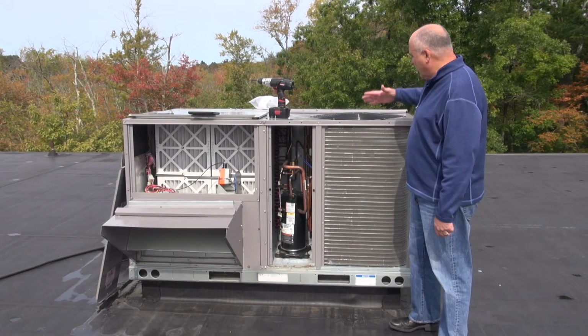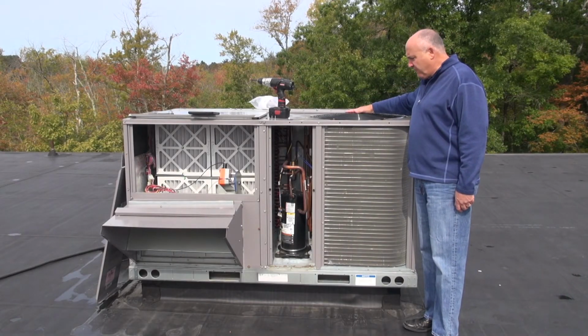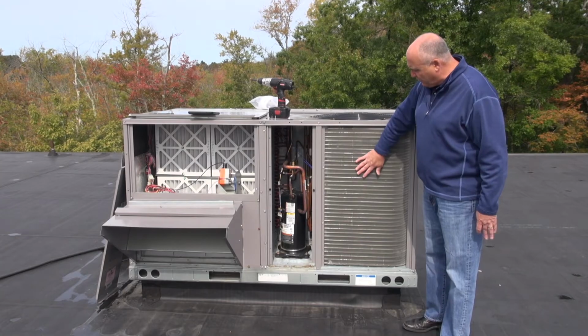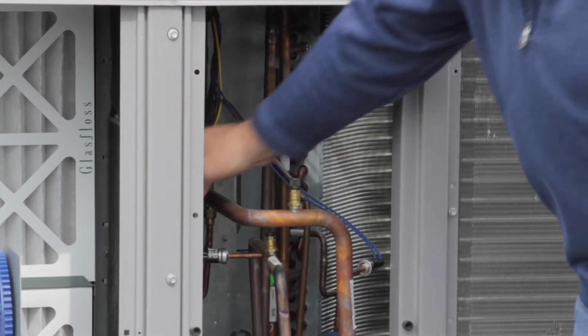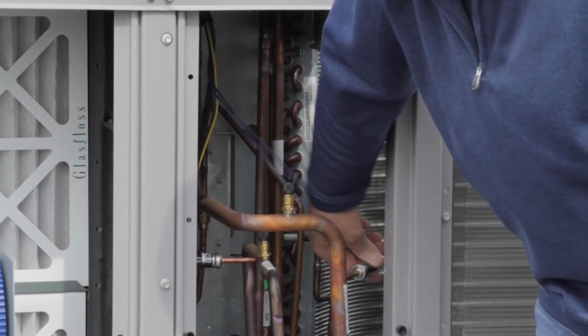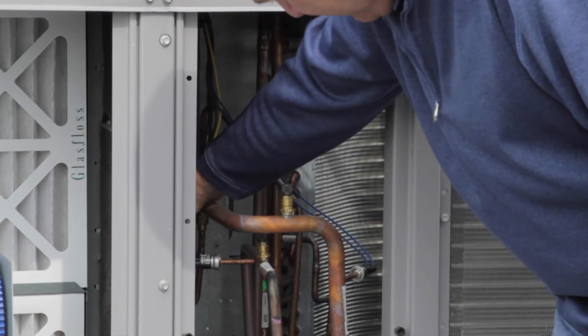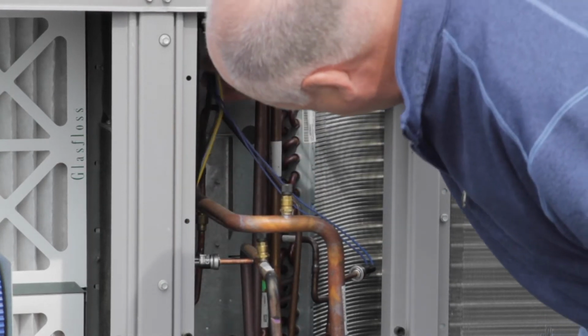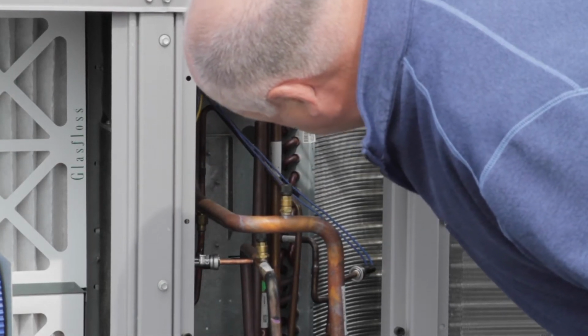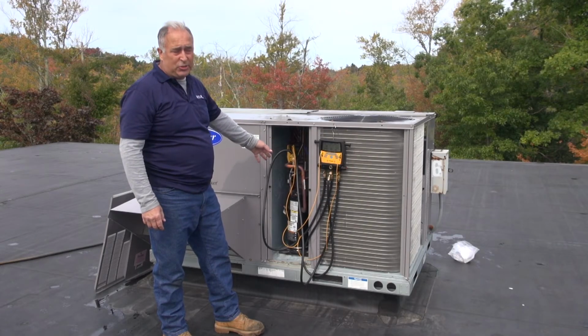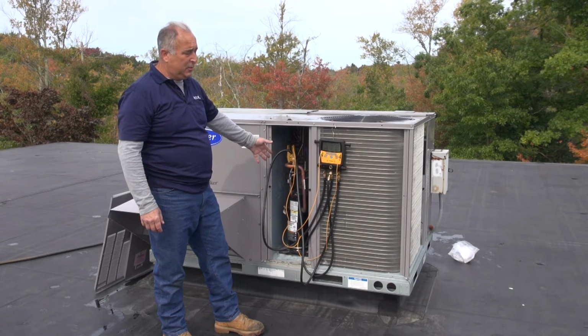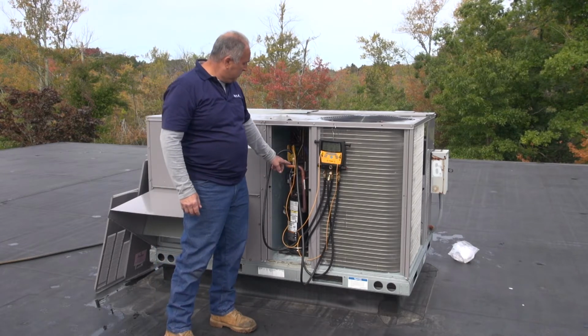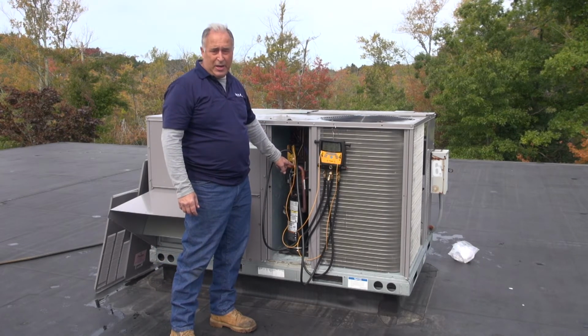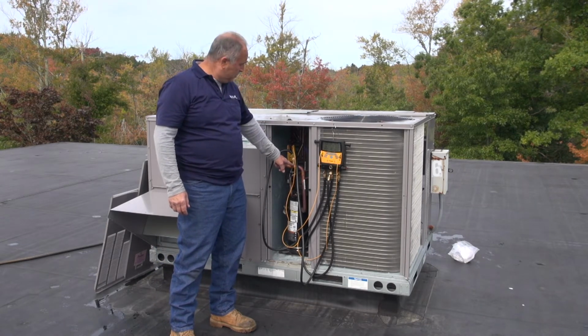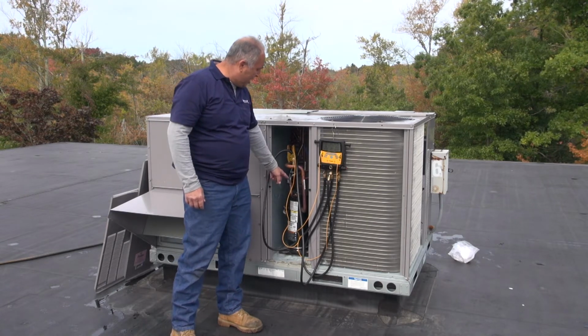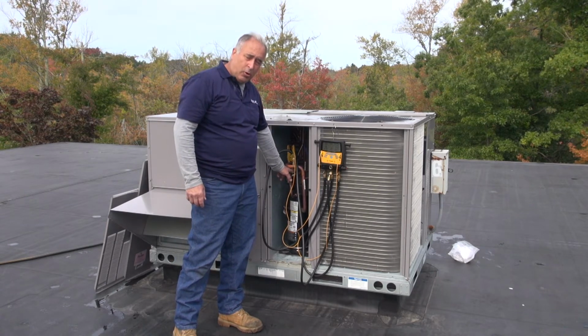In the condenser section of the air conditioning unit, the condenser coil and the fan motor are inspected. The compressor is checked, including the wiring, copper piping, filter dryer, and compressor heater. A pressure check is performed using a gauge which is attached to the suction and discharge ports of the compressor. This measures the pressure of the refrigerant circulating through the machine, and the gauge is set to the exact type of refrigerant in your AC unit.